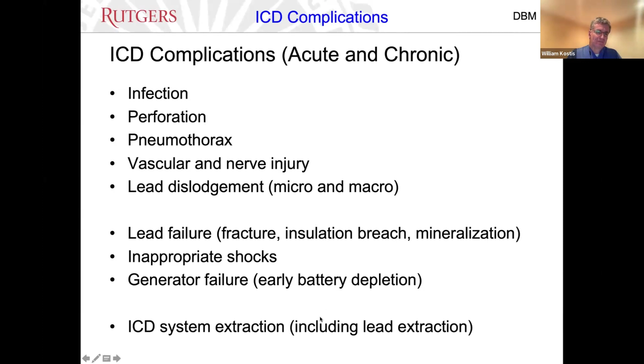So one of the alternatives is to have something called a subcutaneous ICD. There's a pulse generator that gets put in the left lateral thoracic pocket, and a lead is tunneled in the subcutaneous tissues to the left side parasternally. Basically, this can shock the patient when VT is detected. It, however, cannot perform anti-tachycardia pacing. Interestingly, this device can pace in the post-shock period to prevent asystole following defibrillation.